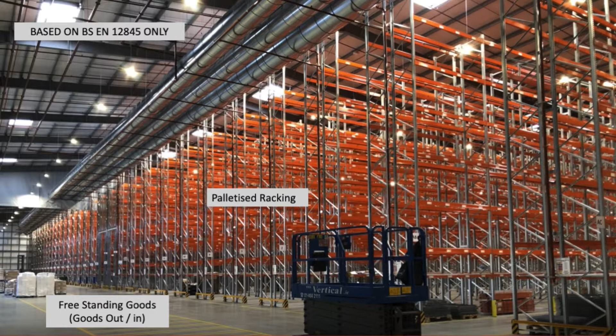So what I'm going to do is base a system like this, where you've got palletized racking on one side and freestanding goods in and goods out on the other, based on EN 12845. For freestanding goods, the distance between the sprinkler head and the top of the goods has to be a minimum of 1 metre and a maximum of 4 metres.